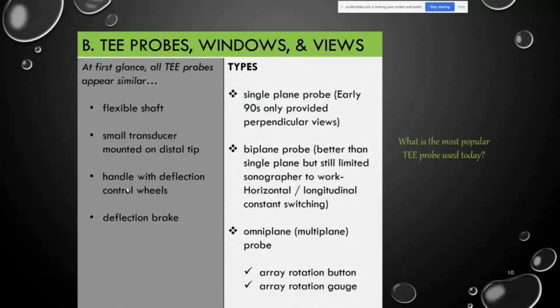So when you first look at the probes, they all look similar. They all have that flexible shaft. They have the small transducer that is mounted at the distal tip, and they have handles with deflection control wheels and a deflection brake. Remember again, the monoplane is that single plane probe that was used in the early 90s, and it gives perpendicular views. The biplane probe came along a little later. It was better than the single plane, but it was limited because the sonographer had to manually change from horizontal to longitudinal, and the views had to consistently be switched until the doctor got what he wanted. The omniplane or multiplane probe has an array rotation button and an array rotation gauge that helps make things easier. That's the one that goes 0 to 180 degrees without us having to do too much. Final thing before I move on from this slide, the most popular TEE probe today is the multiplane probe or the omniplane TEE probe.